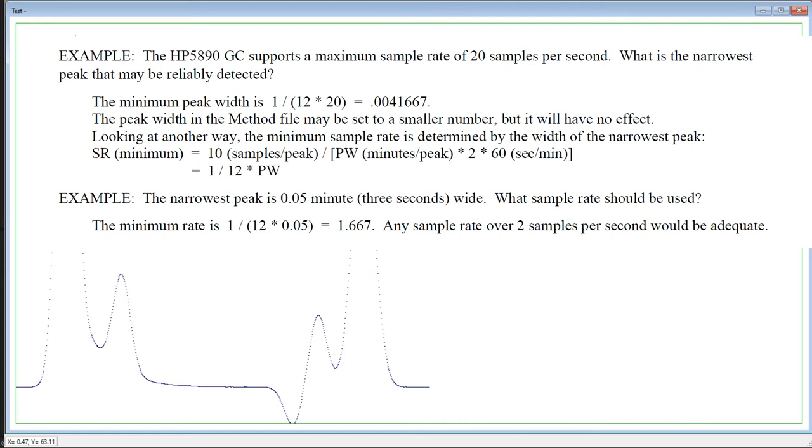Example: the narrowest peak is 0.05 minutes or 3 seconds wide. What sample rate should be used? The minimum rate is 1 divided by 12 multiplied by 0.05 equals 1.667. Any sample rate over 2 samples per second would be adequate.